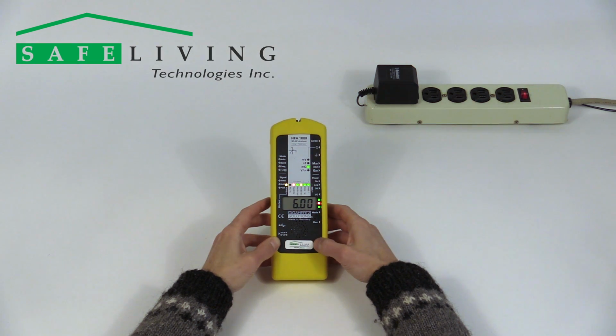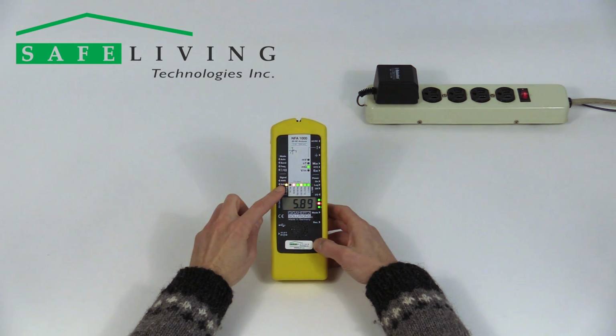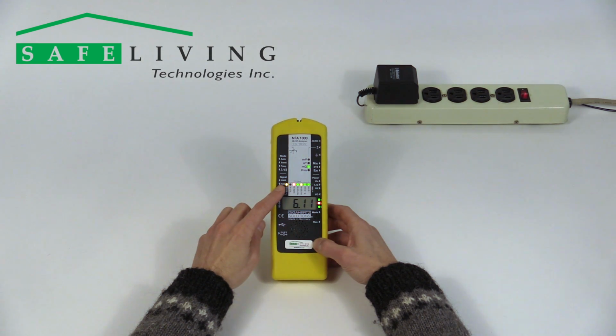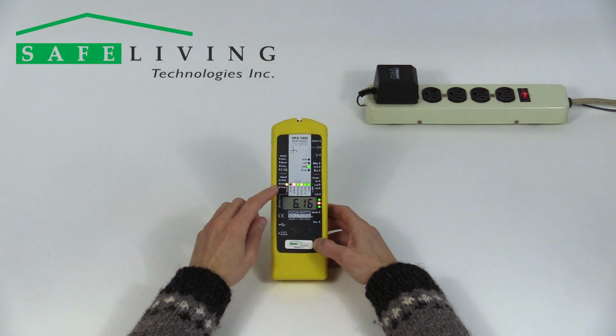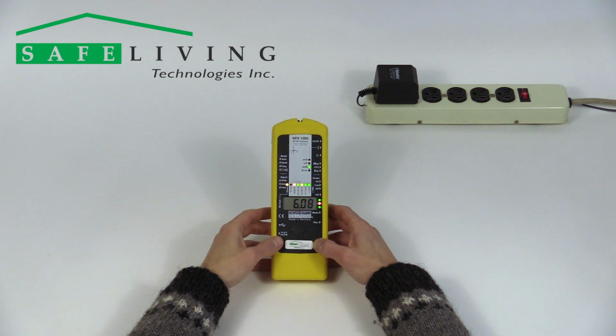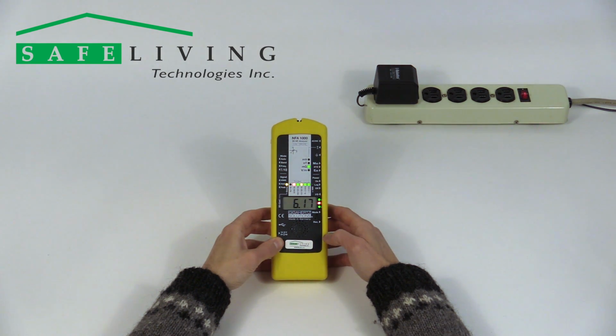Also note the status LED is yellow, showing that we are just measuring and not logging data. A green status LED would indicate that logging is enabled, and a red status LED shows that the meter is charging its battery. Note that when logging without a power source, the status LED will turn off after 15 seconds to conserve battery life.